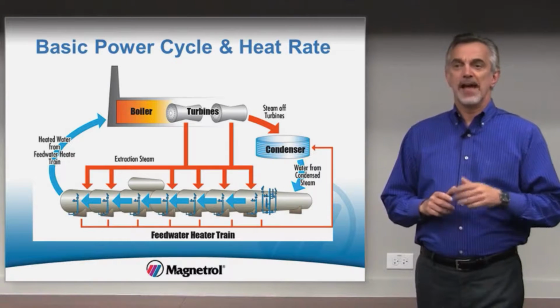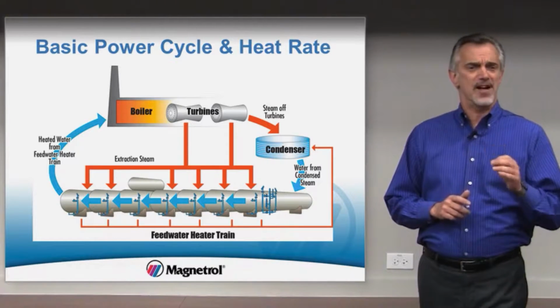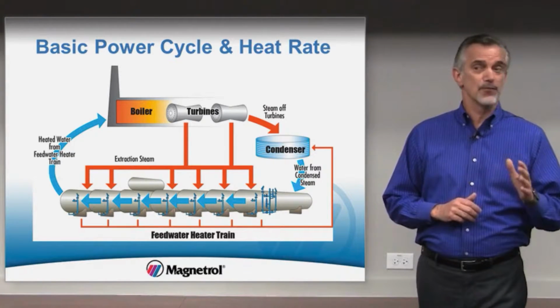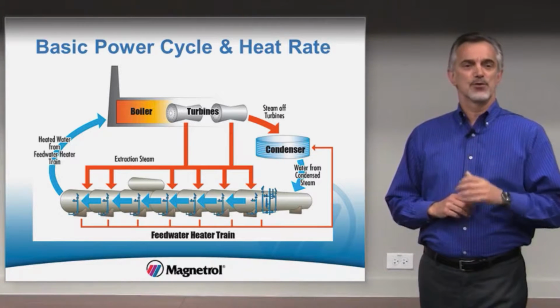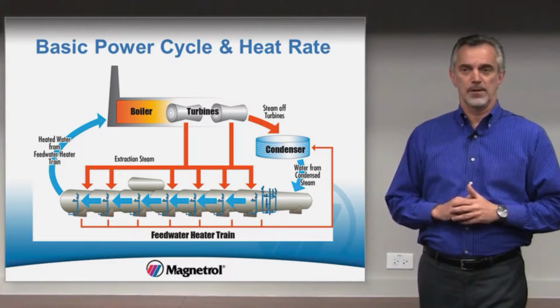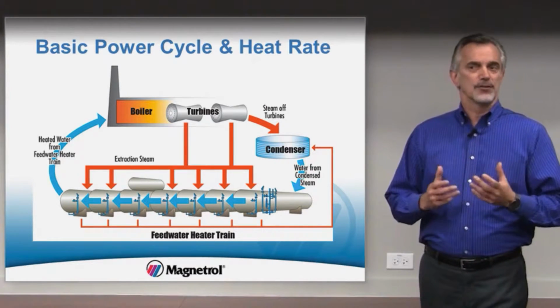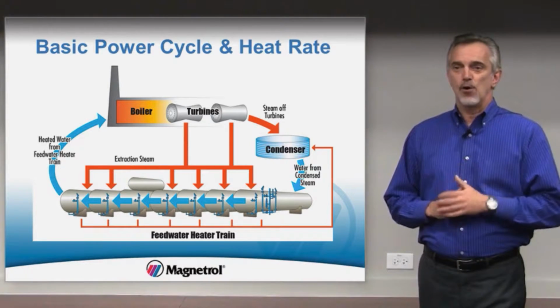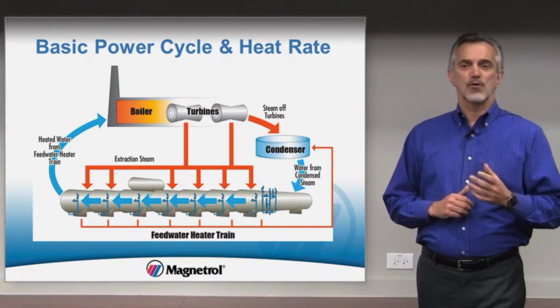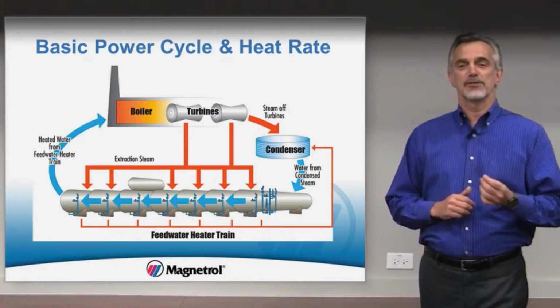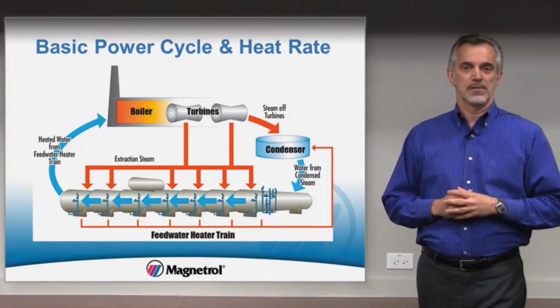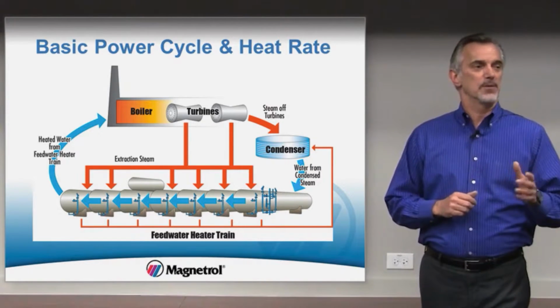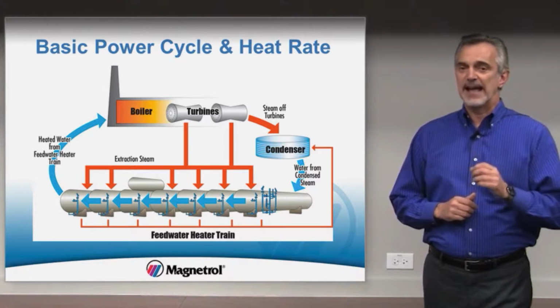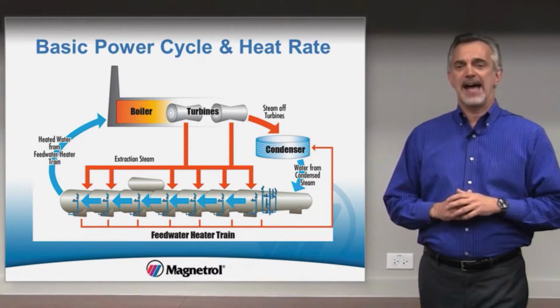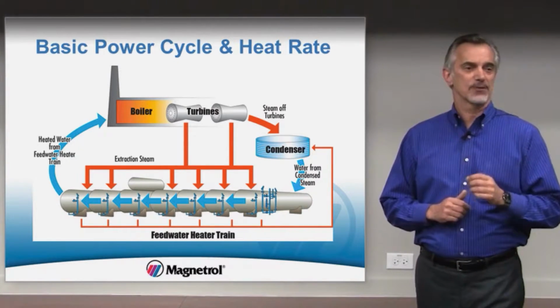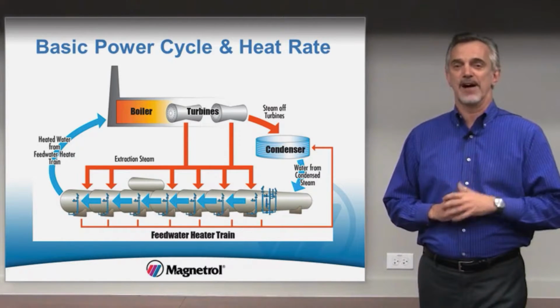For instance, a plant can realize a quantifiable reduction in CO2 and other emissions simply by improving feedwater heater level control. Additionally, extended boiler longevity by eliminating overfiring to overcome shortfalls in final feedwater heater temperature is also achievable. And of course, there is the public relations value in that a plant is pursuing all avenues to minimize negative impact on the local community and environment.